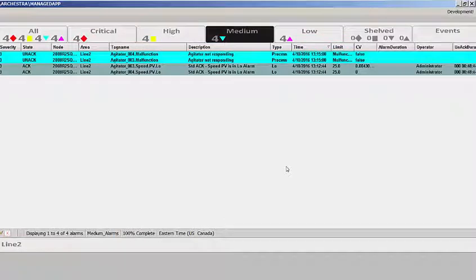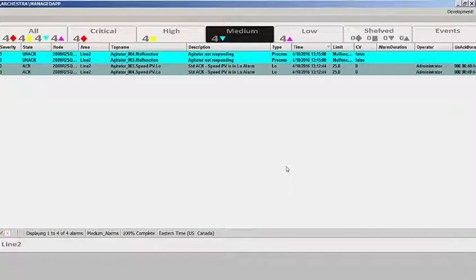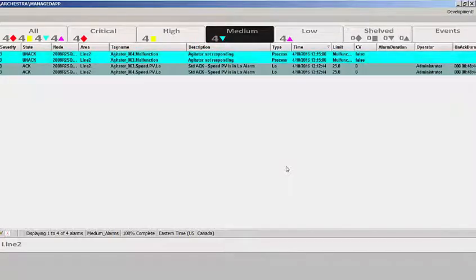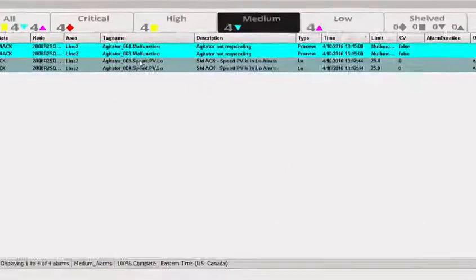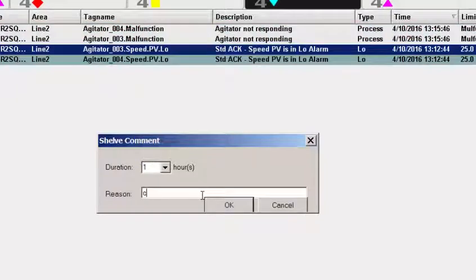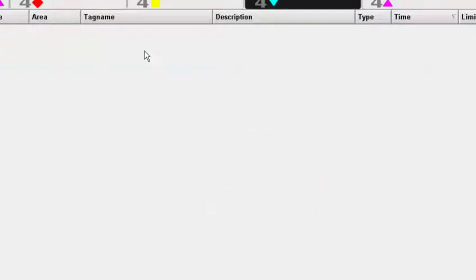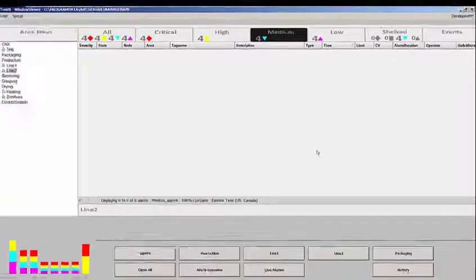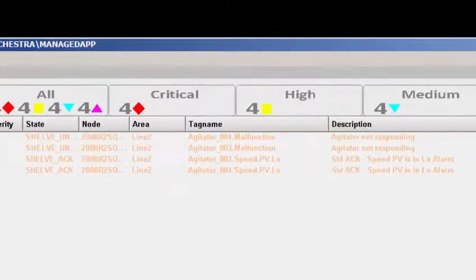Another new feature of our alarm subsystem is the ability to shelve an alarm. Shelving an alarm is important because we don't want to overload operators with nuisance alarms — for example, during maintenance or calibration on a piece of equipment. So the ability to temporarily shelve an alarm is important. If I right-click on this alarm banner, I can say I want to shelve all these visible alarms, give it a reason such as calibration mode, and they disappear from my main screen. Looking at the shelved filter, it confirms these alarms are now shelved and won't annunciate on the screen.